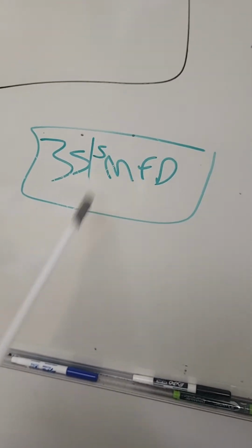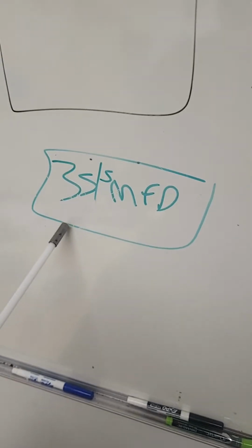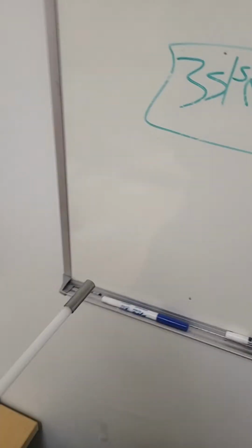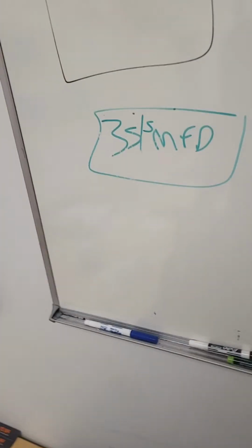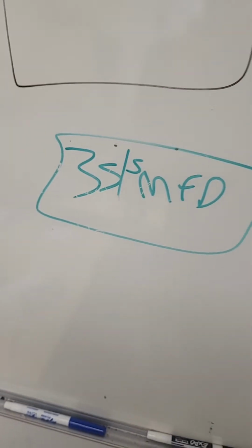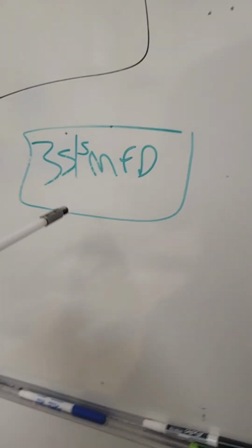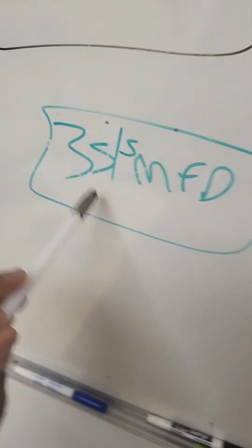Using the same example, if you have a 35-5 cap, the highest tolerance I would recommend is probably 5 microfarads on either end, but it's like a 24-hour window. If I have a 35-5 microfarad dual cap that's bad, a 40-5 cap could work, but make sure you can come back with a 35-5 cap within 24 hours.